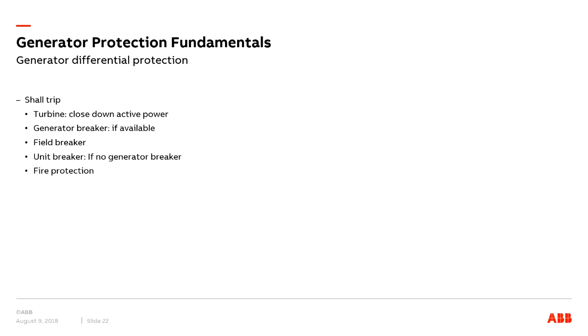So what does a generator differential protection do? If a differential protection picks up, it is due to an internal fault in the generator. This means that the plant must be shut down as fast as possible, and no attempt for house load operation shall be made. And we need to trip the turbine control system, which will control the active power from the turbine to the generator. It will be reduced as fast as possible, and other different actions are made depending on the type of the power plant.